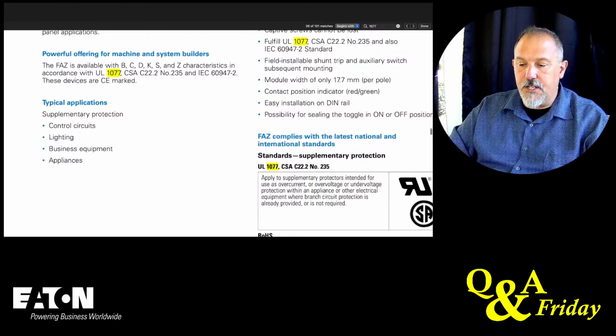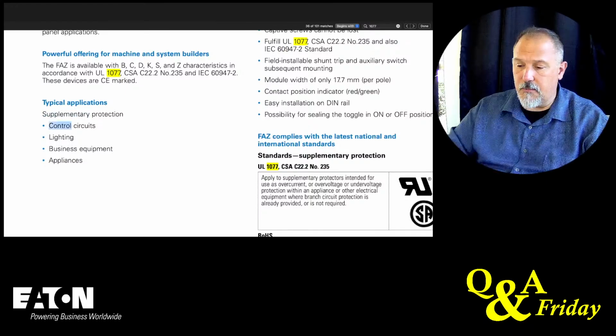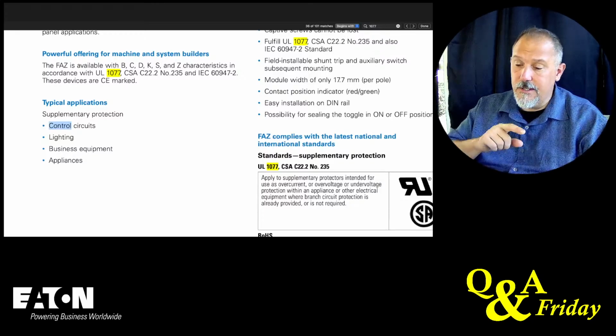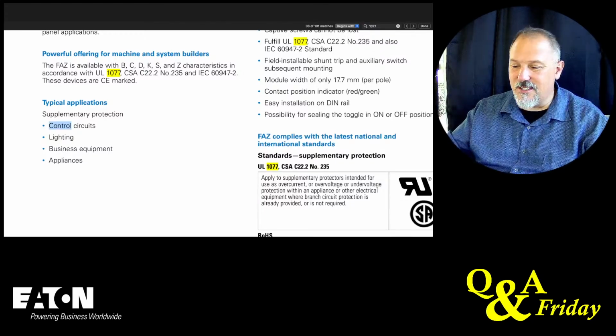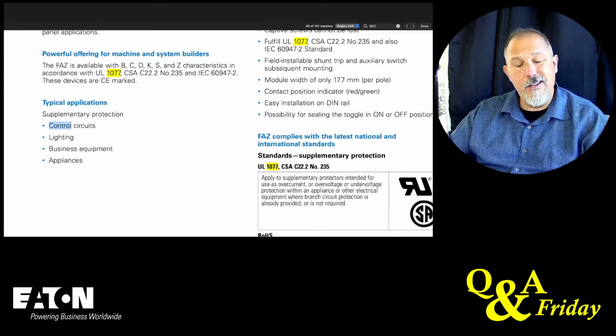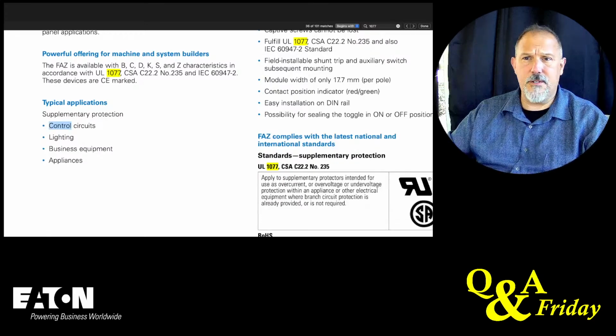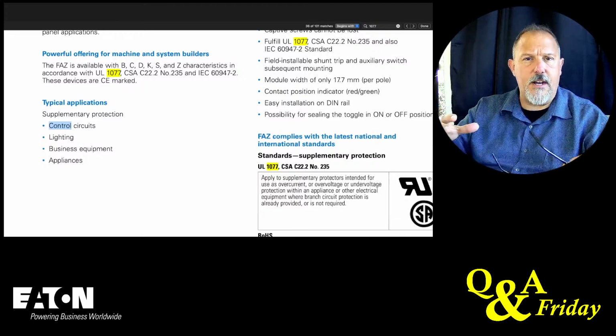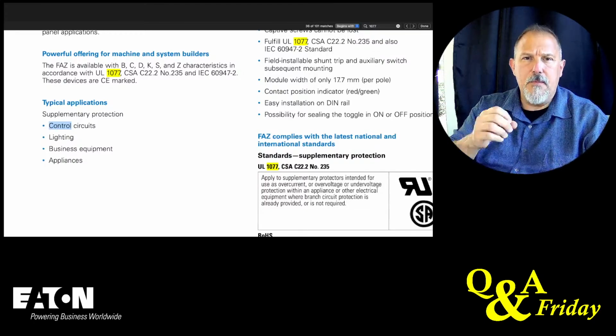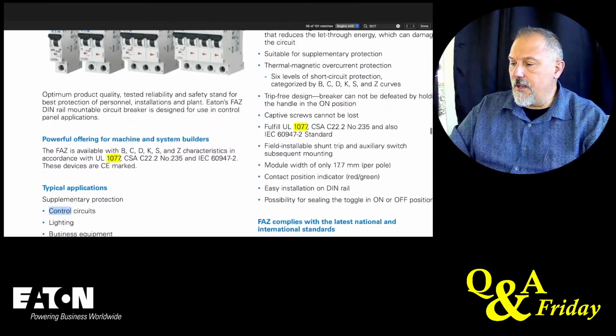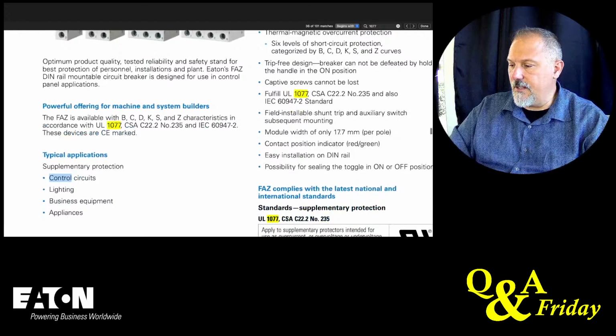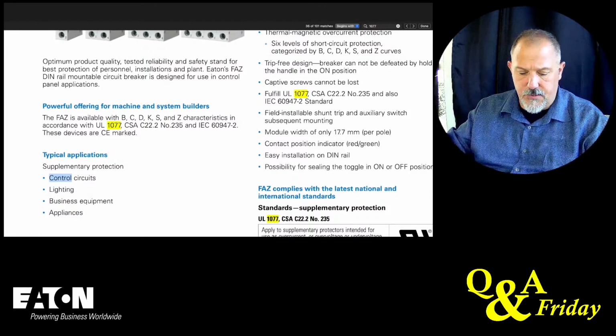So typical applications: supplementary protection, control circuits, we already talked about that, lighting. Never thought about that one, did you? Business equipment. When I hear business equipment, I might be thinking printers, copiers, things like that, and appliances. So those are the types of equipment where you'll find supplementary overcurrent protective devices that might be a 1077 device. They're listed to UL 1077, CSA C22.2 number 235, and also IEC 60947-2. Those are different standards for different countries, and we've got a few of those countries represented.